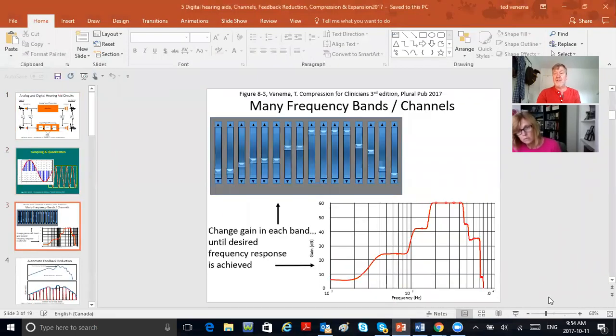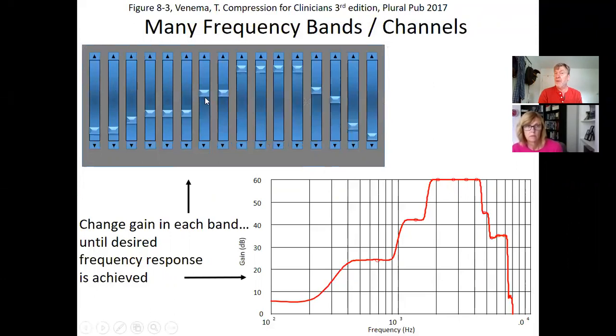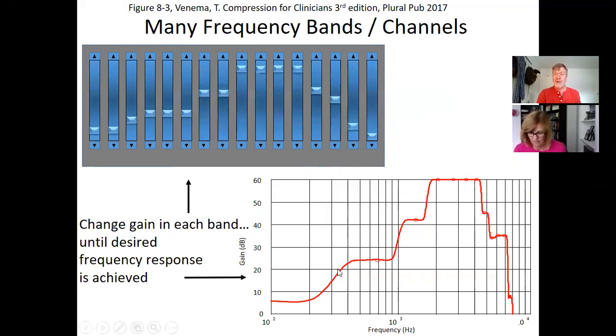Today's digital hearing aids have many more channels or bands. Instead of three, you might have 15 — some have 25 — and the channels become really narrow. The more channels you have, the more fine frequency flexibility. The frequency response can be literally sculpted to anything you want, making today's digital hearing aids extremely flexible.